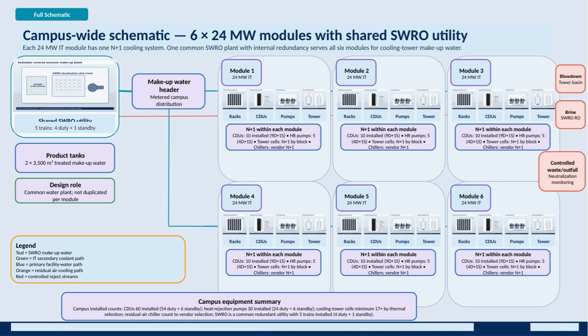Color coding in the schematic helps differentiate systems. Teal indicates SWRO makeup water. Green represents the IT secondary coolant path. Blue marks the primary facility water path. Orange shows the air cooling residual paths, and red outlines controlled reject streams.